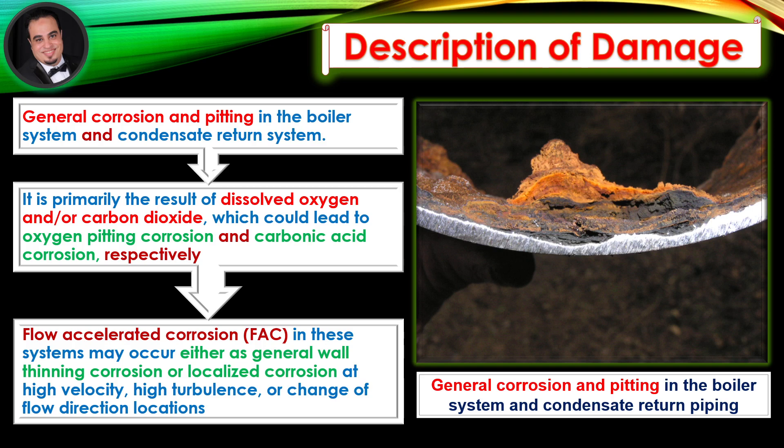Flow accelerated corrosion in these systems may occur either as general wall thinning corrosion or localized corrosion, at high velocity, high turbulence, or change of flow direction locations.